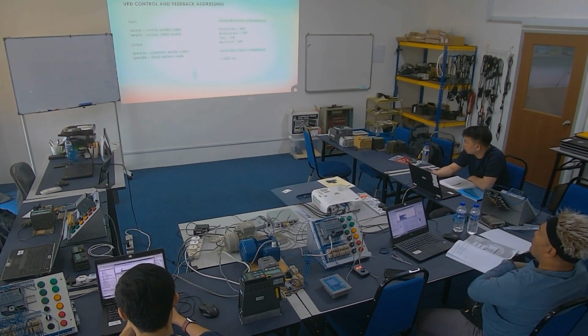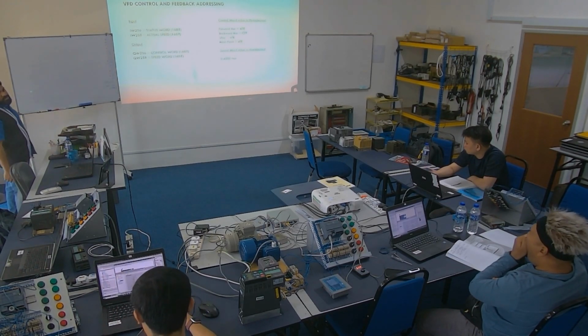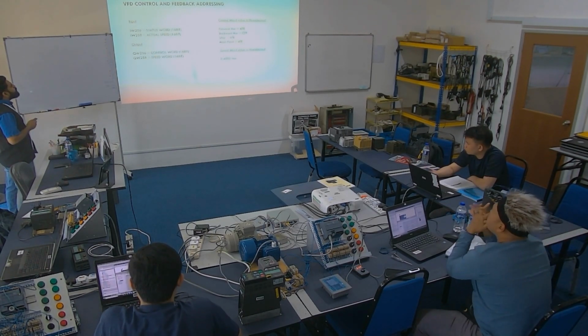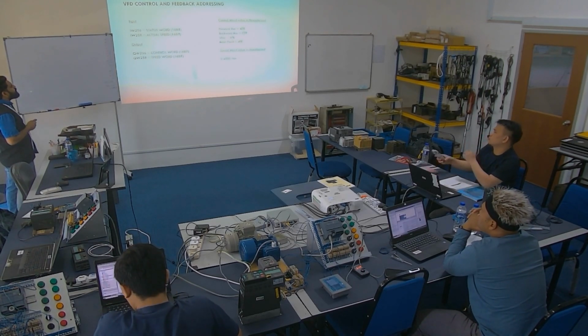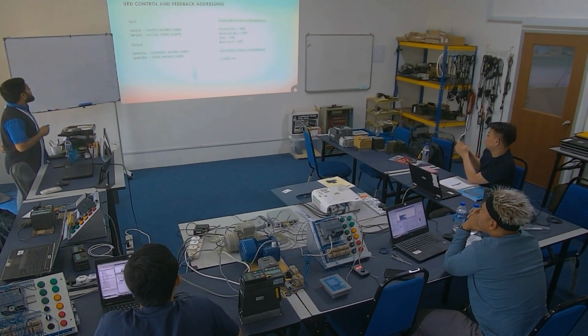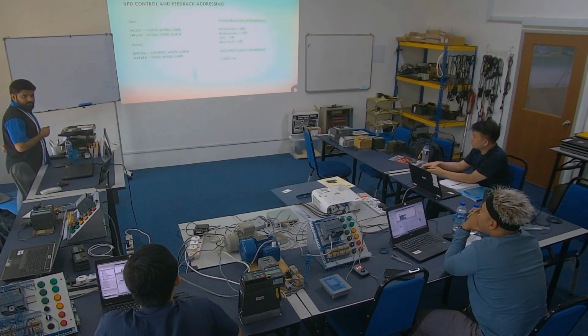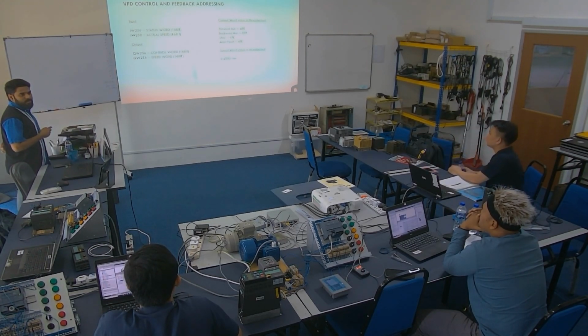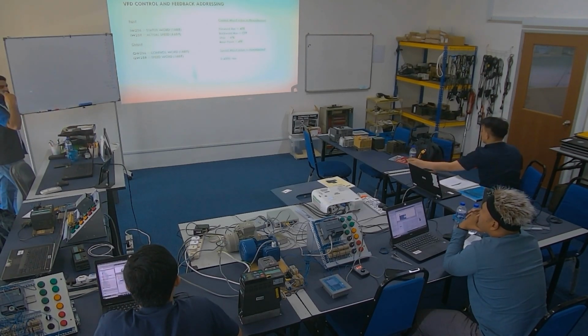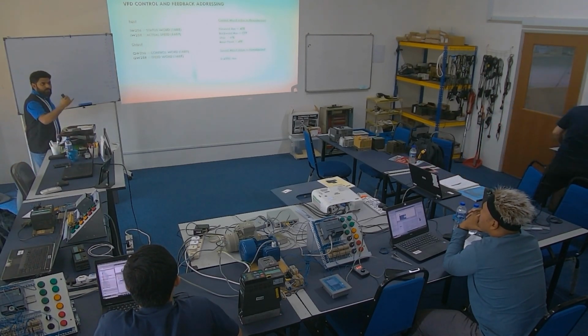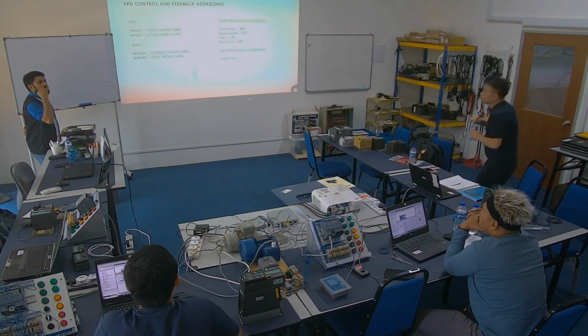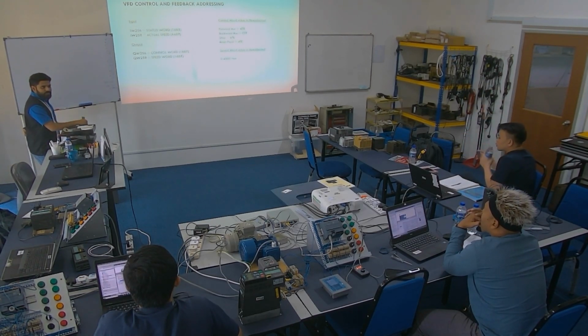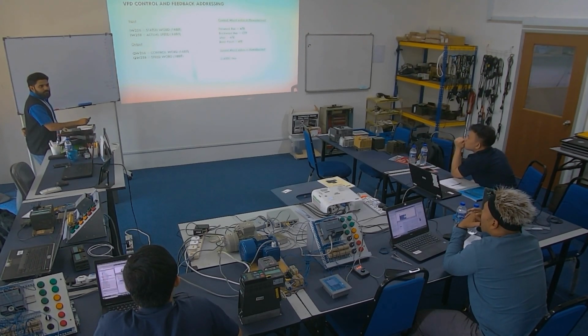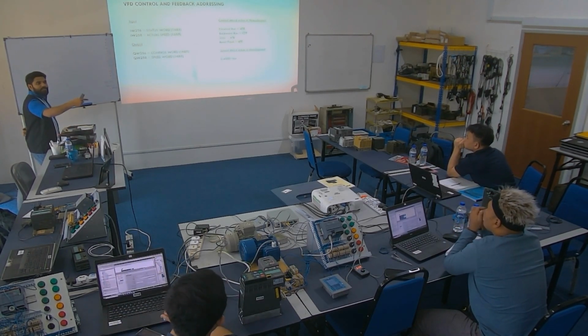These are the data of your PLC. So input got two, right, 256, since it's 16-bit it's IW256. The first one is actually the status word, meaning to see whether the motor is running, stopped, running forward, running backward, all that. The second one is the actual speed, meaning what the motor is currently running at, the current speed.